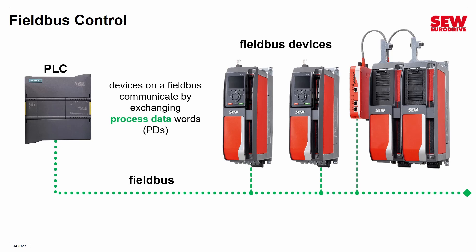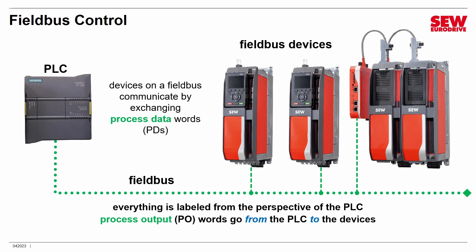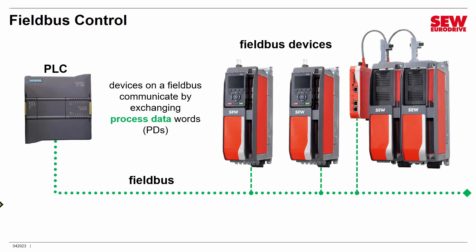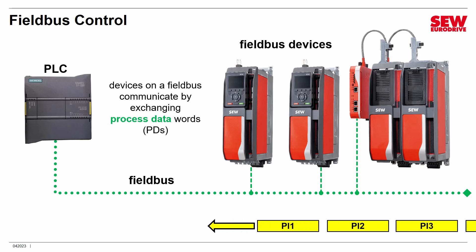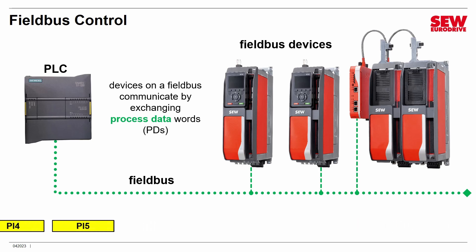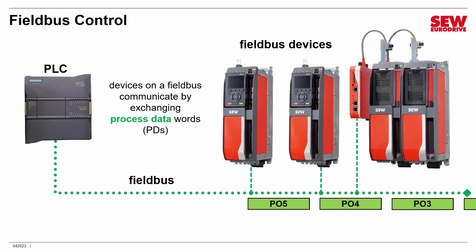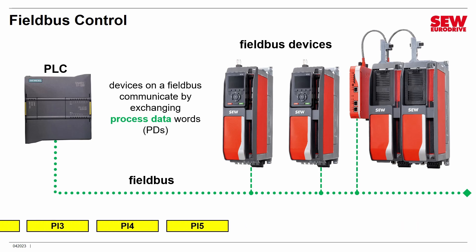Devices on field buses communicate by exchanging process data words — 16-bit words that go back and forth between the PLC and the devices. Everything is labeled from the PLC's perspective: process output words go from the PLC to the devices, and process input words go from the devices back to the PLC.